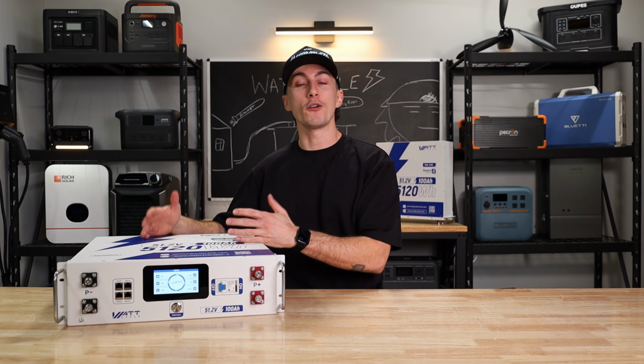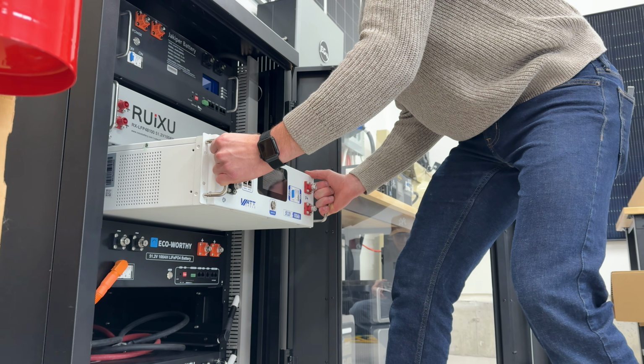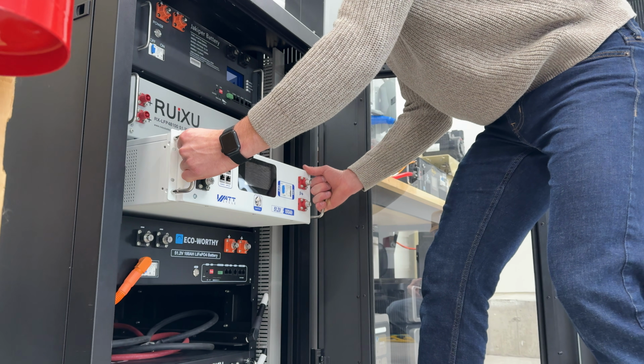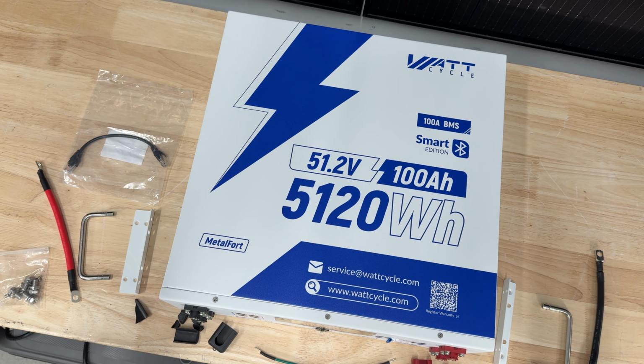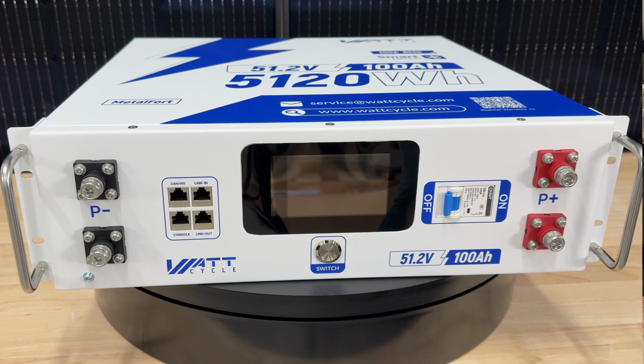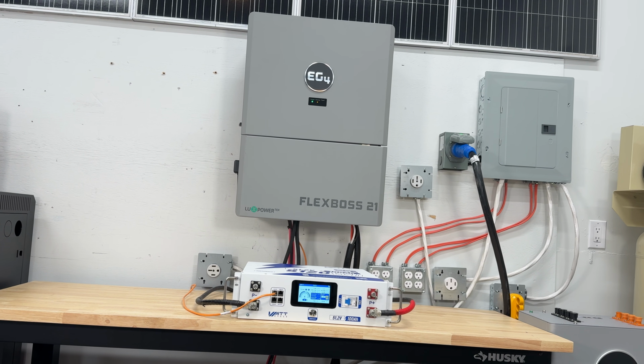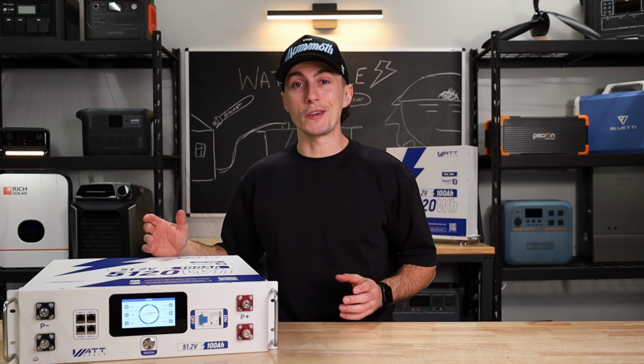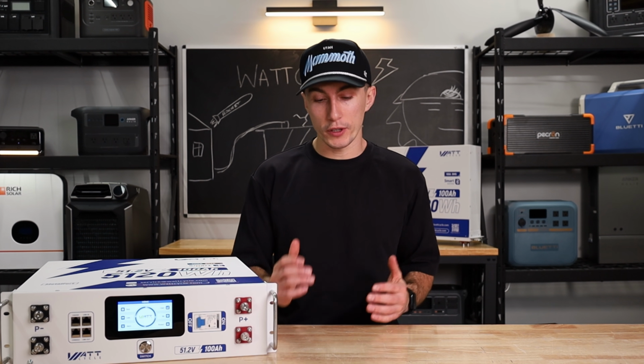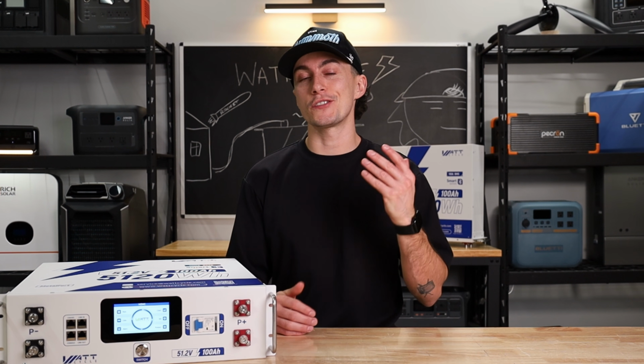It has a continuous output of 100 amps, and you can parallel up to 20 of these guys to have a max system of over 100 kilowatt hours of total storage. This battery has a max output and input of 100 amps, which basically means you could charge this thing from 0 to full in about an hour and discharge it just as fast.